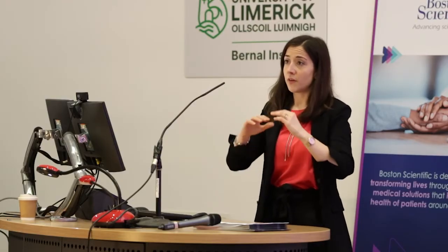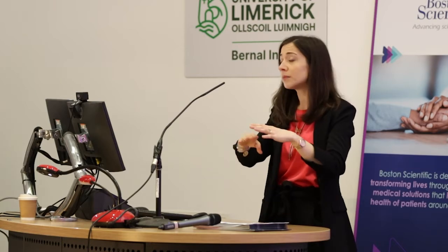So even if the metal foil is made up of titanium, there are laser weldings on it, and one of the worries is that the laser welds behave like a different type of material, so a different type of metal. So the worry was that there could be potential galvanic corrosion between the normal grade 5 titanium and the laser welded. So it's important in this case to study if corrosion can happen, because we need to predict the impact of corrosion and how this affects the life of the device.